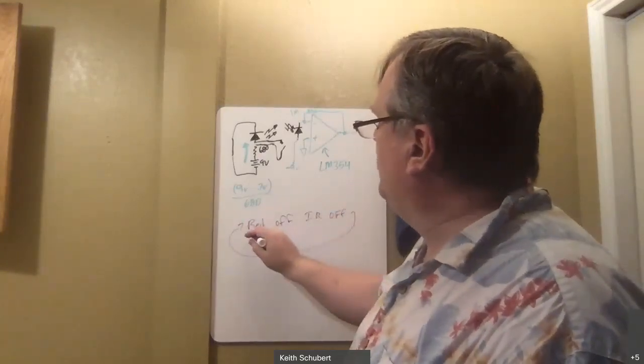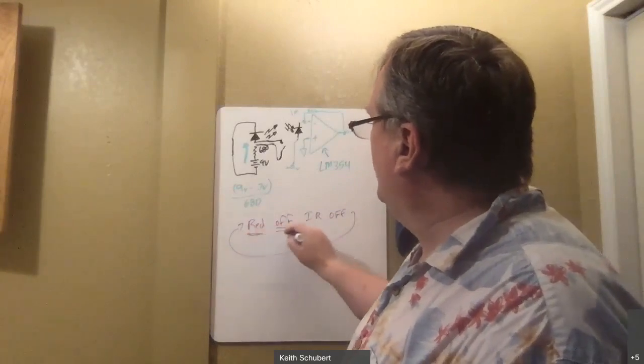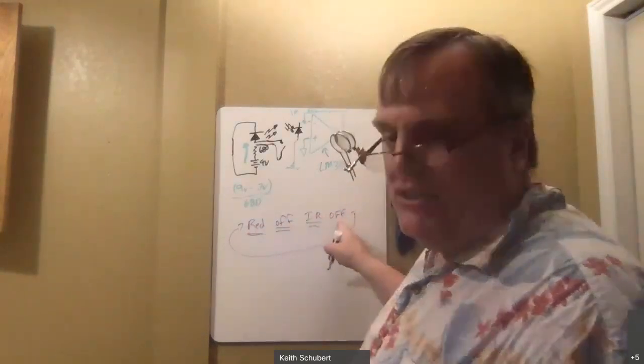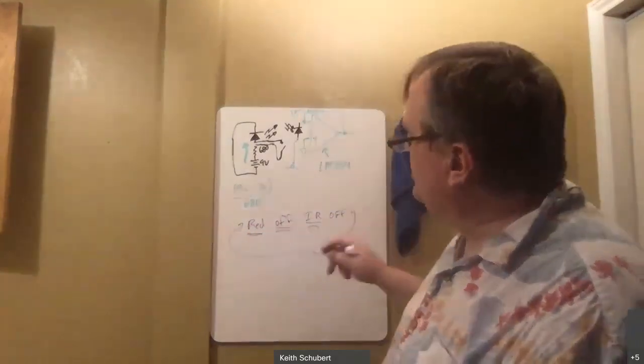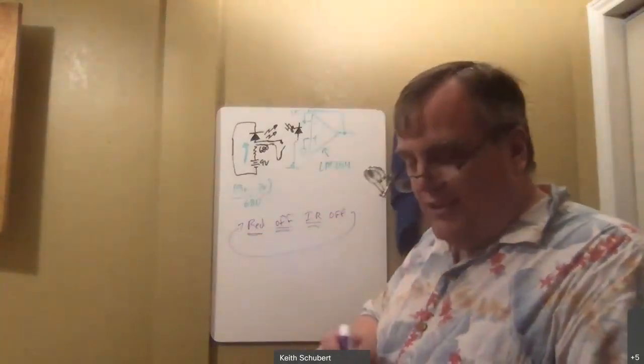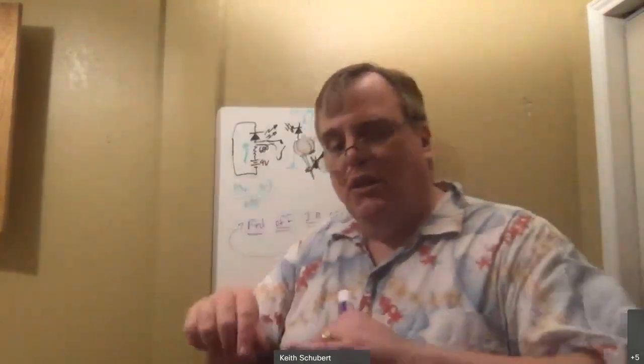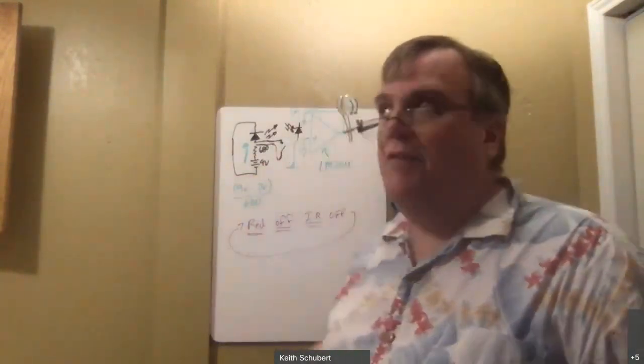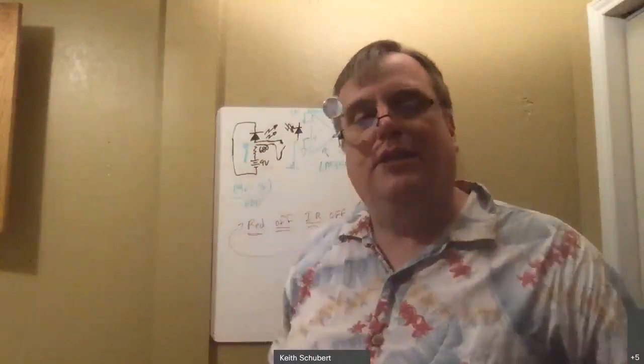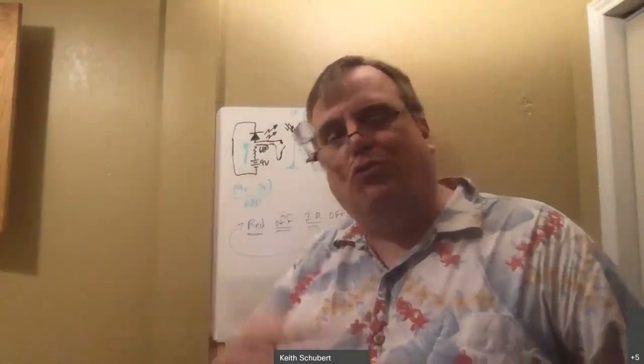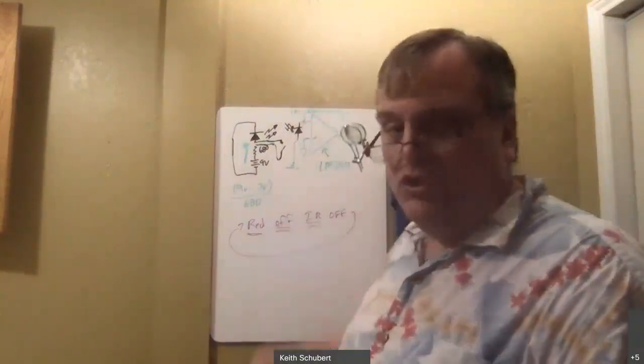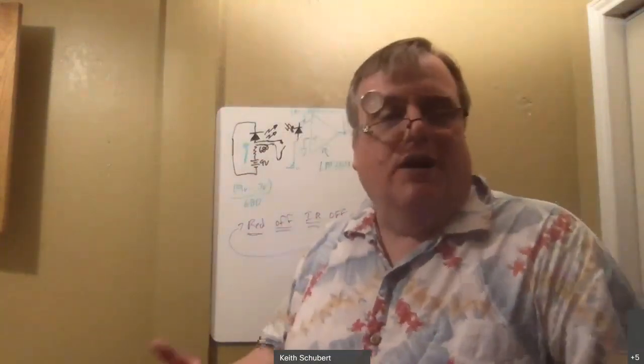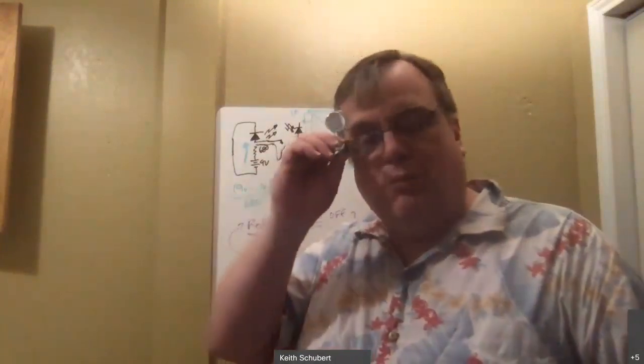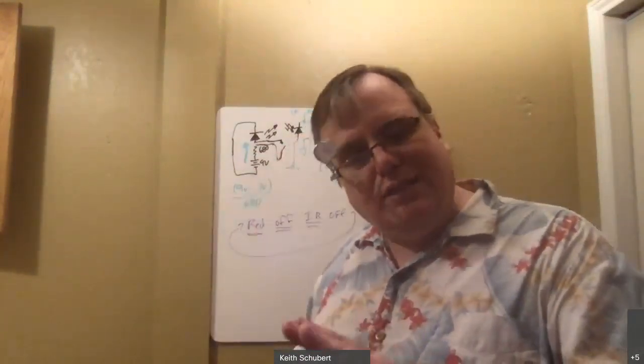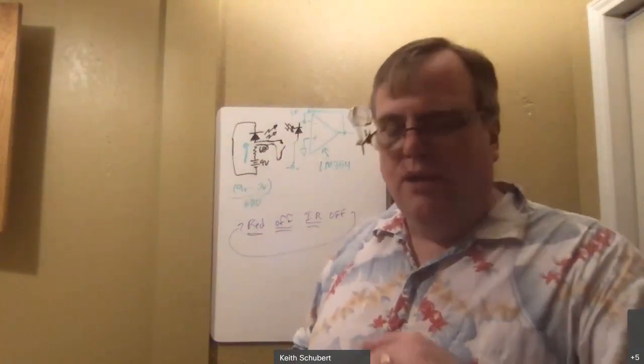Typically what people will do is they'll measure on the red and off and infrared, and that's just a wait state. The reason you measure the off is because, remember I said, all the light coming in from the sides? That light still goes through my finger into the detector. If you measure it when both of these are off, you've got a measure of how much light is coming in the sides, and so you can just subtract that off. You kind of filter it, so you smooth it. You find out what the constant value is, assuming that light's not changing too much. And hopefully the person's staying still because they have to get a good measure anyway.